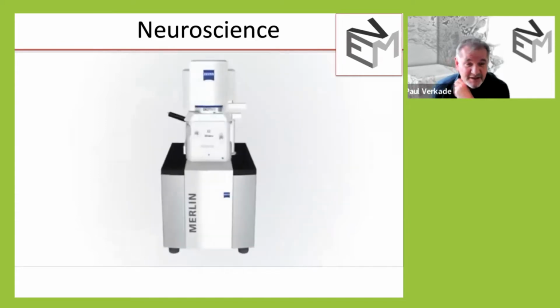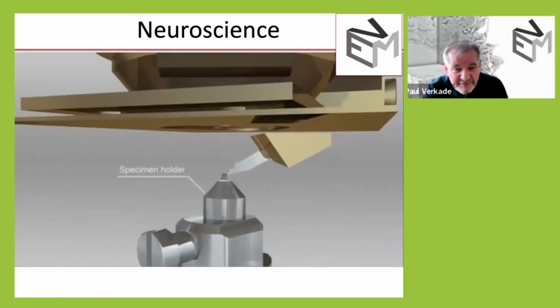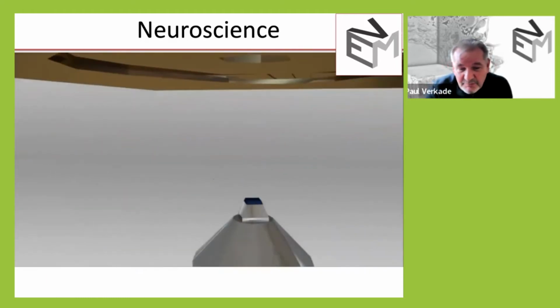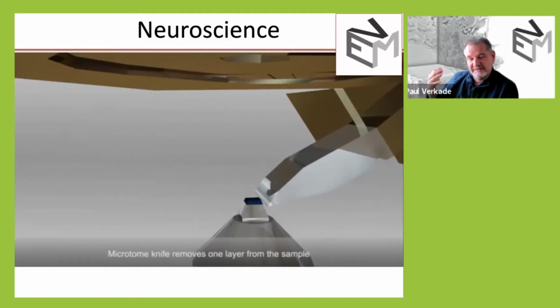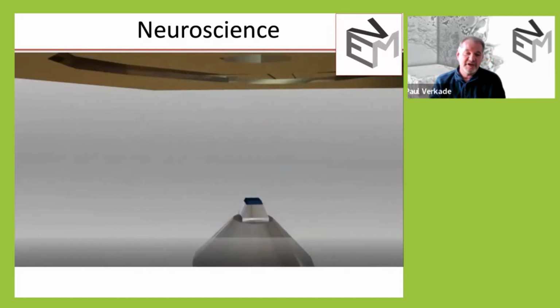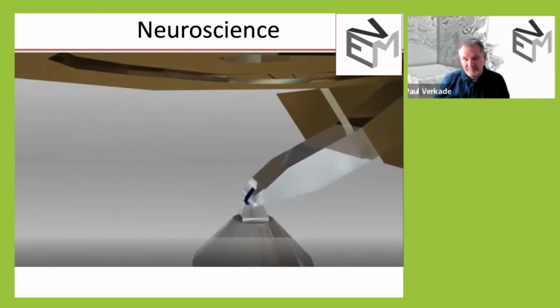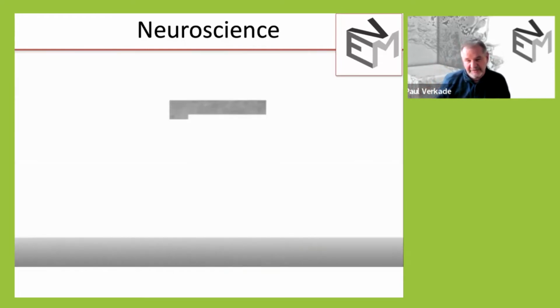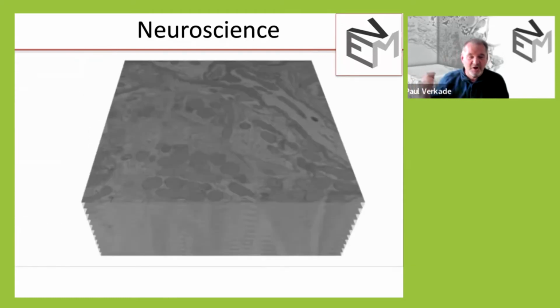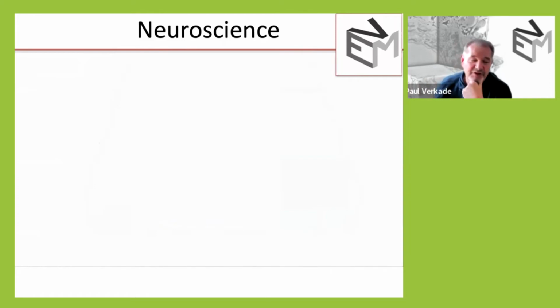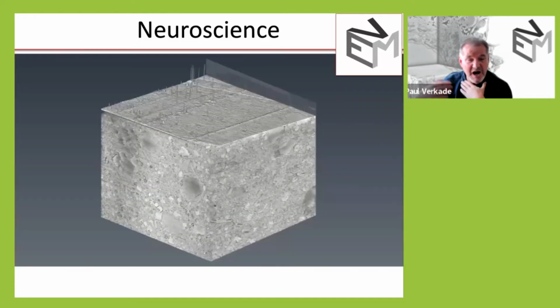and it's sped up. It's about 5 times faster than what it was meant to be, and this is from Zeiss with a Gatan 3View system in there. What it has is they've built a microtome inside the scanning electron microscope. It scans the top surface, then slices off that top and scans it again. And that's repeated over and over again. And by that, you can build and collect hundreds, thousands of sections if you want, and build up a real 3D structure. And so that's what we did for our structure as well.